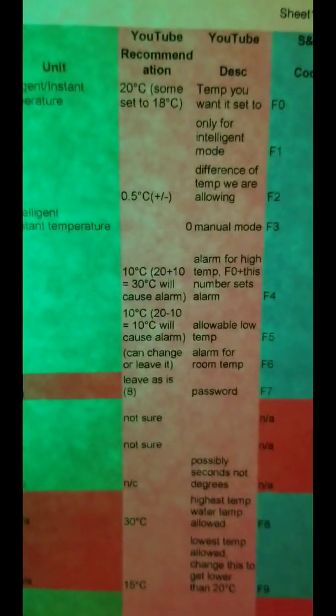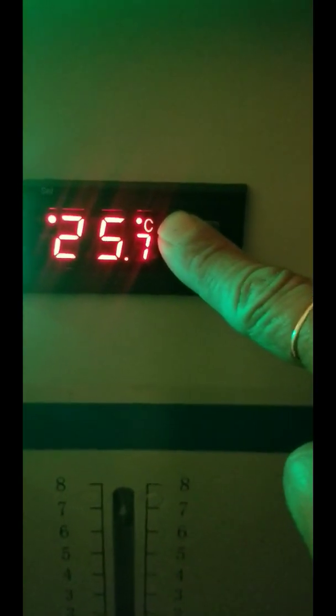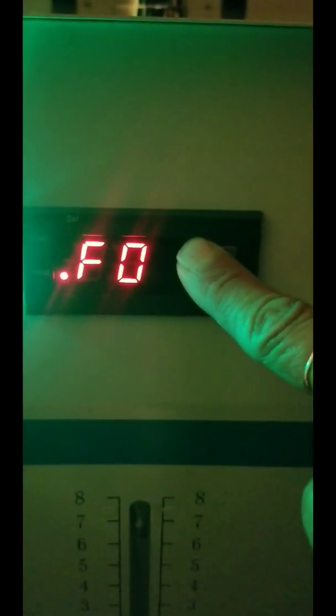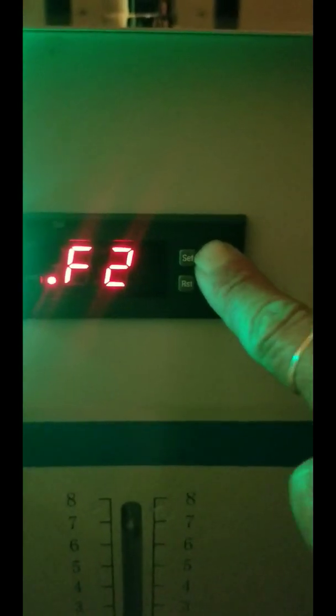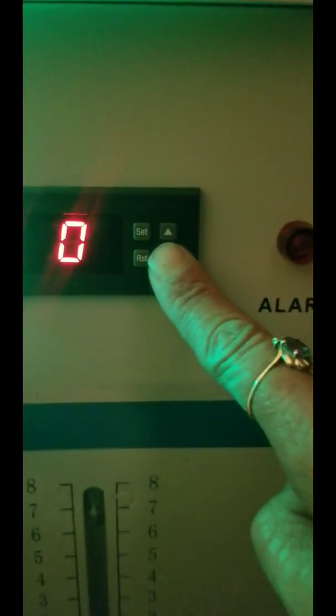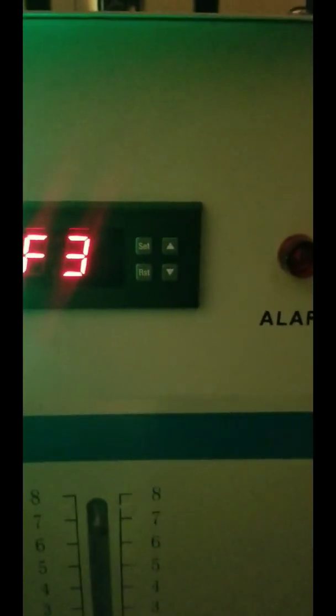F3 is control mode — zero or one. One is for intelligent mode; zero is for instant temperature, which is the manual mode. So we want zero. You would do the same for an S&A machine. Navigate to F3, press SET to select, change it to zero, and press SET.